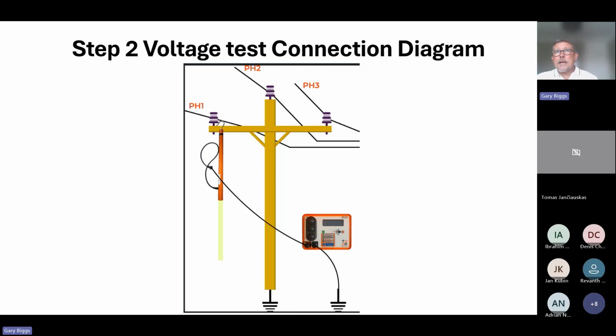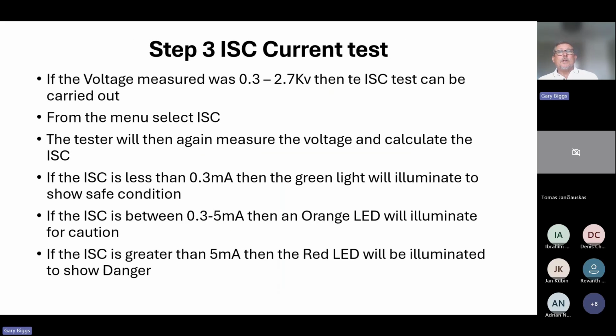So this is quite an arduous task, to find these leaky insulators. If we were doing a current test, and the measured voltage is between 300 volts and 2.7 kV, then we would carry out an ISC test to find out what the prospective short circuit current is at this point. From the menu on the display, you would select ISC. The tester will then again measure the voltage, and at that point it will calculate the ISC.